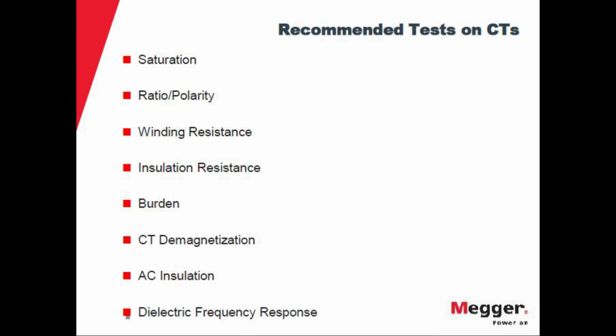So, a long time ago, these used to be done with separate instruments. You would have a variac for the saturation test. You would use that variac also to do the ratio and the polarity, but in a different way. For winding resistance, you need a DC current source. Then you need a separate instrument to perform the insulation resistance. In the demagnetization, you also probably needed something else. So usually testing CTs was very demanding on the instruments that you needed, and it would take a lot of time to perform the test.